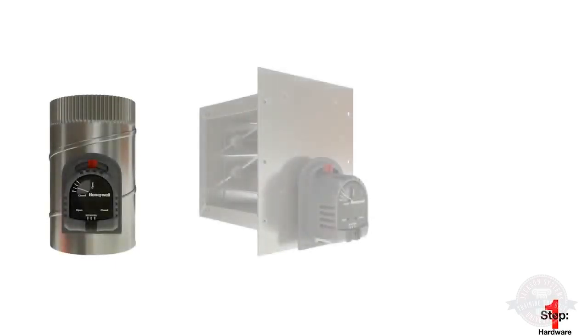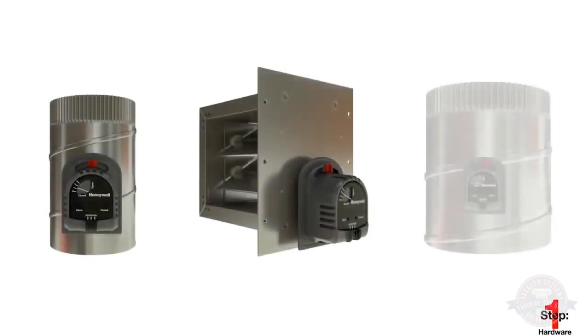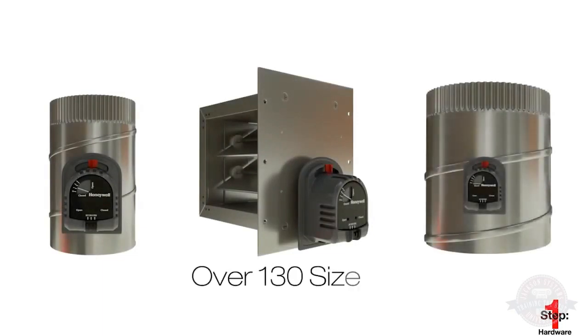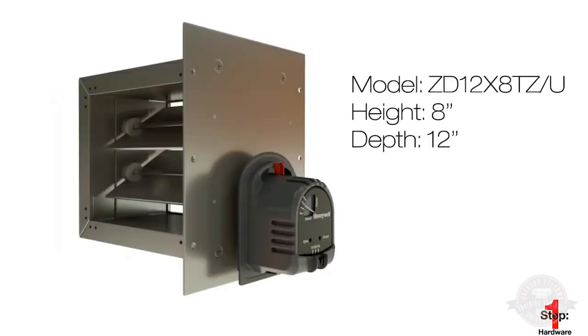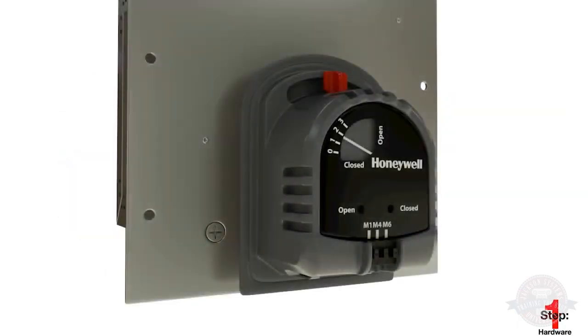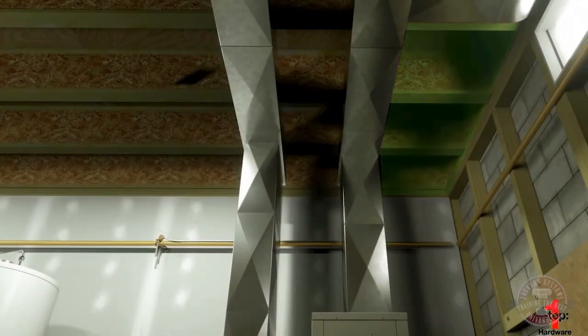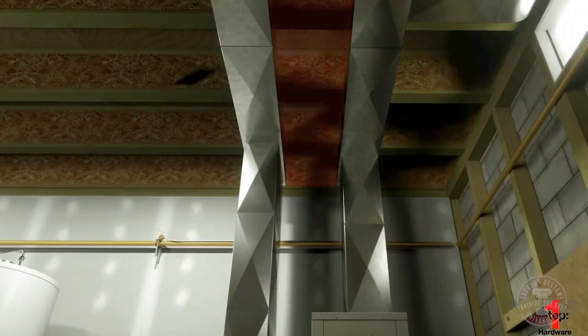Before starting the installation, make sure you've selected the proper size for the job. TrueZone dampers are available in over 130 sizes, making it easy to meet nearly all application needs. When ordering a square damper, note that the motor is mounted on the second dimension. There are several types of TrueZone dampers. Each has a unique installation procedure, but all share the same actuator. For all TrueZone dampers, be sure to position the actuator in an accessible place for wiring and servicing.